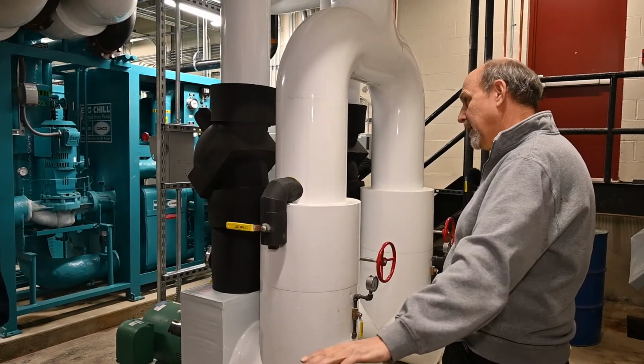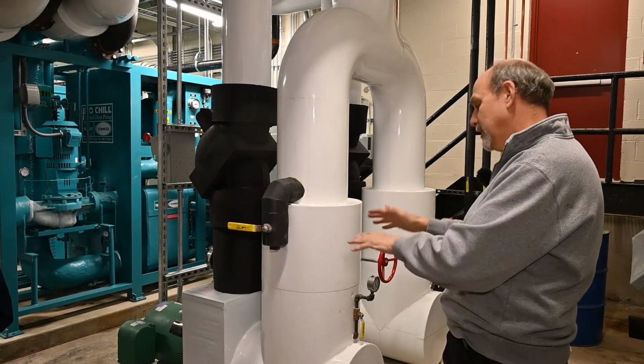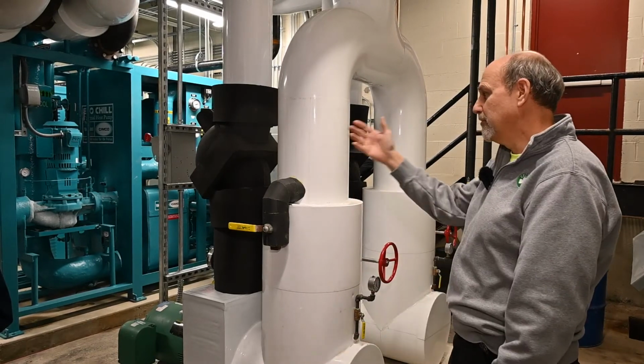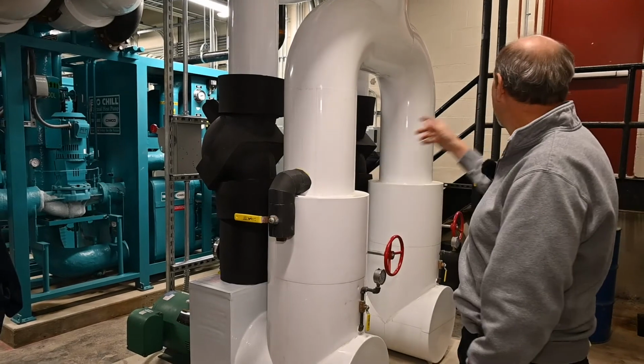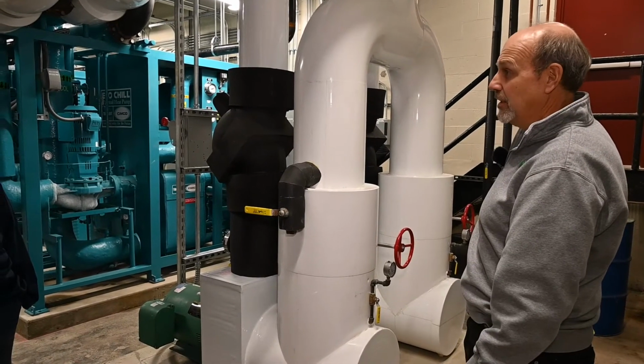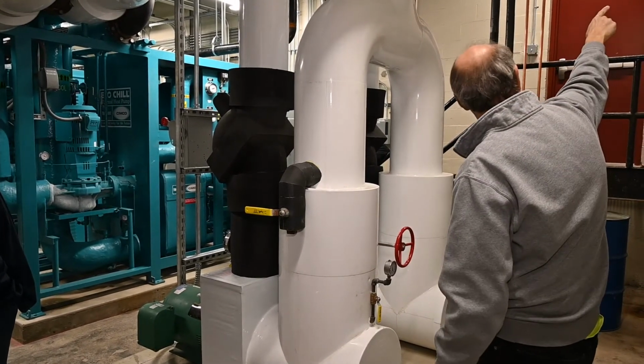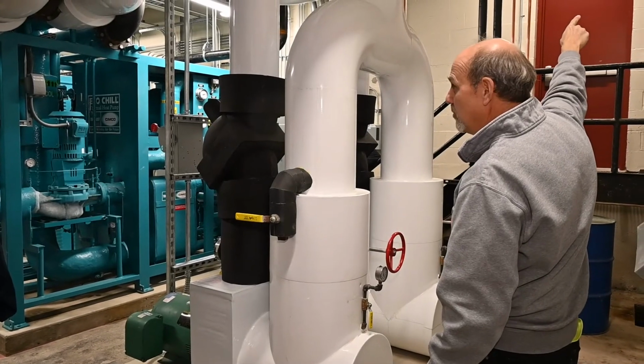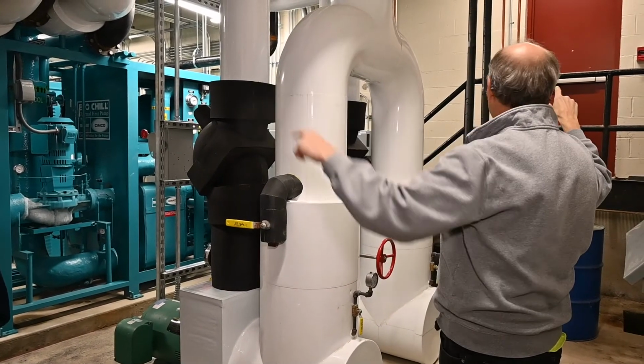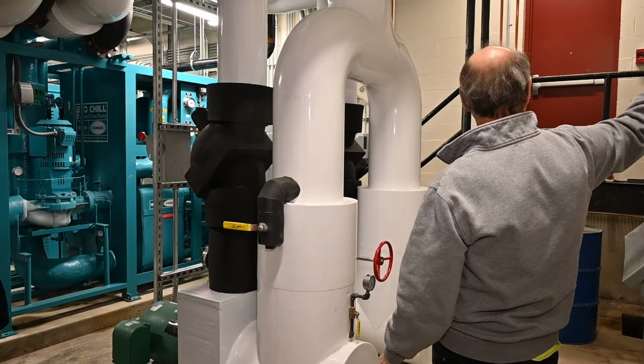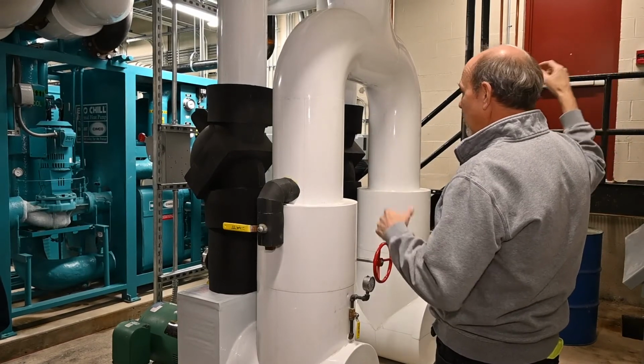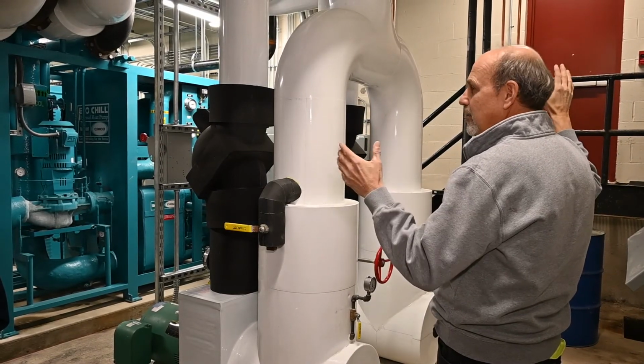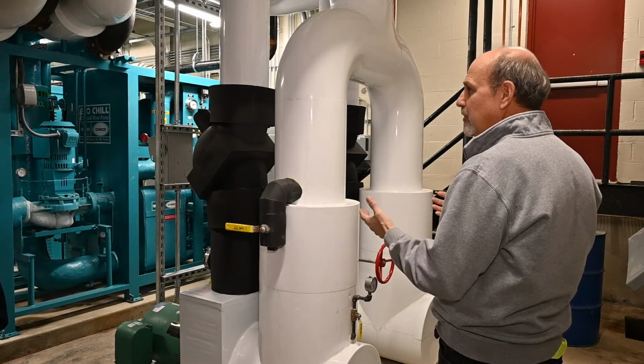Refrigerant's a little bit lower than air as far as where it goes, so if it does leak out, it's going to gravitate to the floor. The refrigerant sensor would pick that up, and right outside this door is an alarm panel. That blue beacon that you see up there is a horn strobe. There's one outside the building, one outside this door, and one outside this door, 4 of them total. If you see those going off, you've got a refrigerant leak, you've got a refrigerant problem.